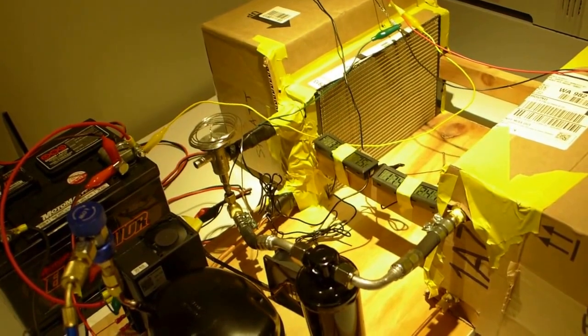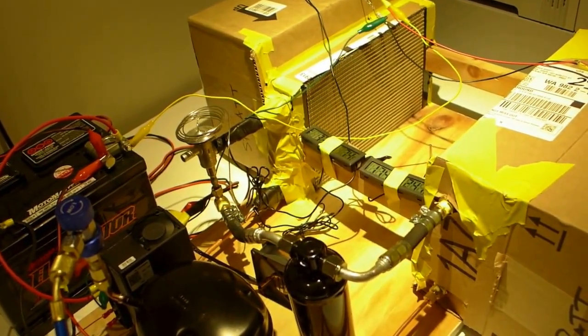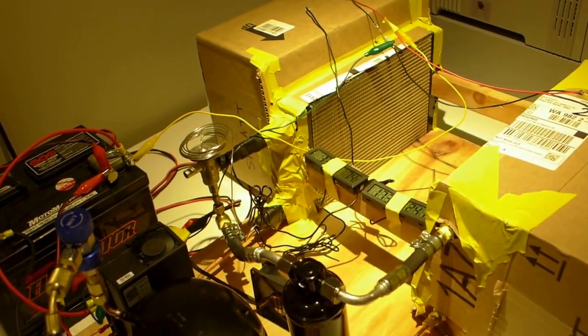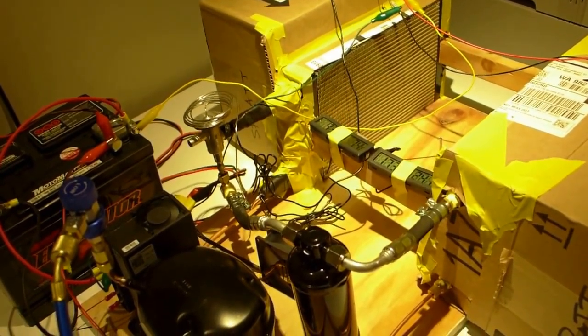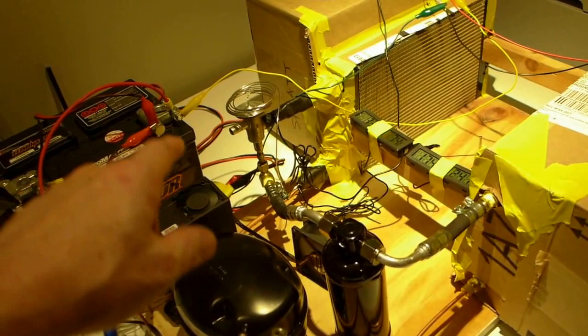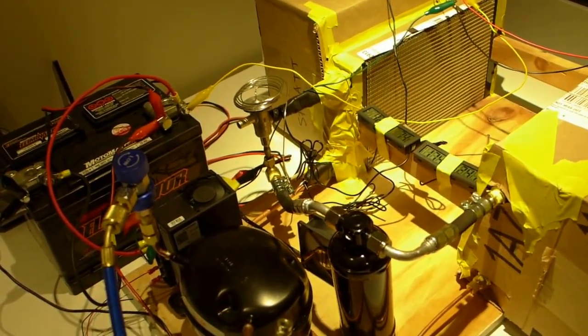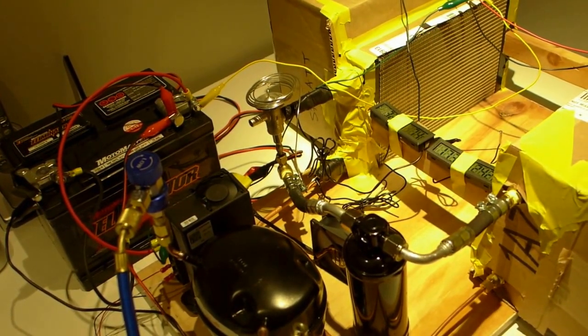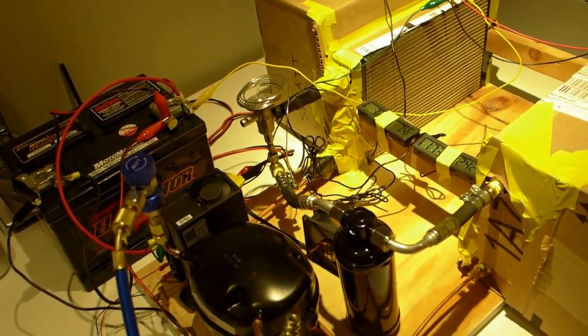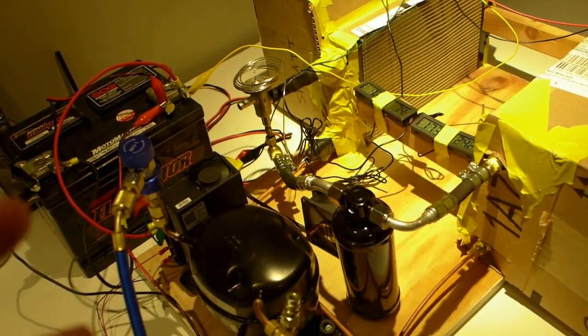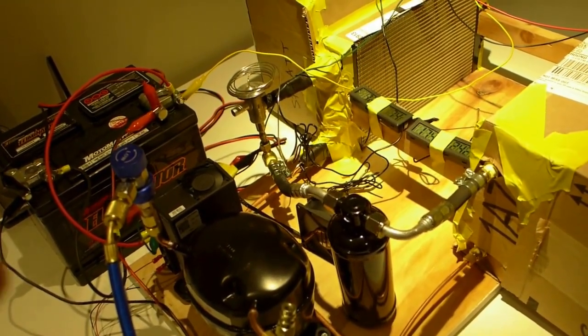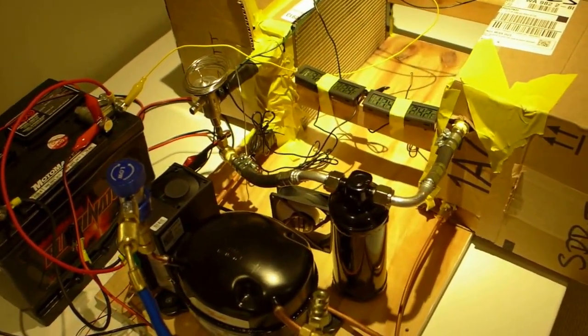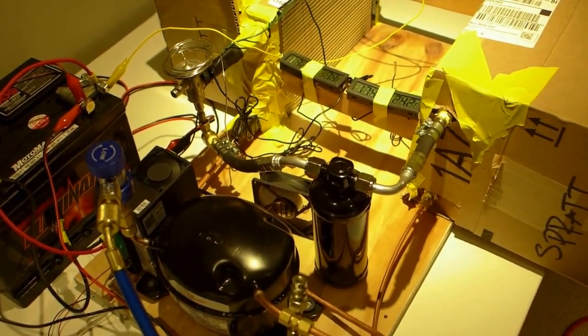So it's interesting, I can take the refrigerant level really, really far down. And then the pump just stops consuming current because it's not doing any work. And then the temperature coming out of the thermal expansion valve will actually go negative. It will get down to like minus two or minus three degrees Celsius. But it's just barely spitting anything out. And so when you crank the system up, it's not getting as cold going into or out of the evaporator. But it's pulling more net energy out of the air as you can see with a good six and a half degree differential.